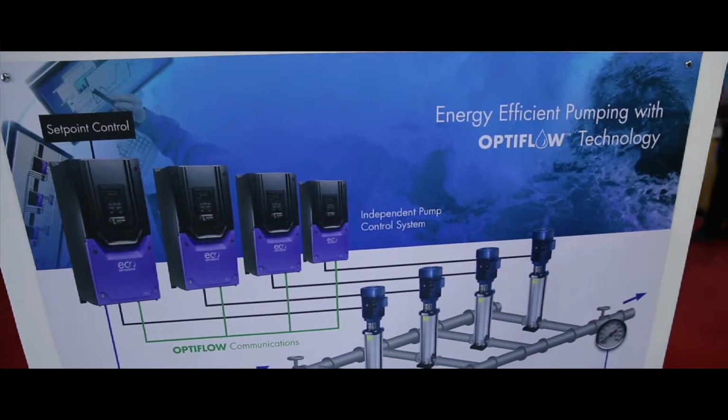And there's a few parameters that we need to configure then to say when we want to start the second pump and when we want to stop the second pump. And the system takes care of itself, because the drives operate in slave mode and take the speed reference from the master. The biggest concern with most of our customers with any system like this is redundancy, as we have the pressure transducer connected only to one inverter, the master. But our system is configured in a very clever way that means that the master, even if it loses its power connections, retains the control, because on the communications connection we actively maintain the 24-volt control, and the signal will continue to operate and stage in the pumps as required and stage them out as required. So it's been a very, very popular feature for giving fantastic energy saving solutions for secondary pump solution.